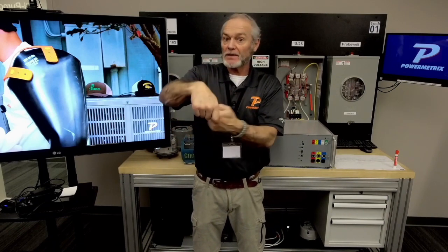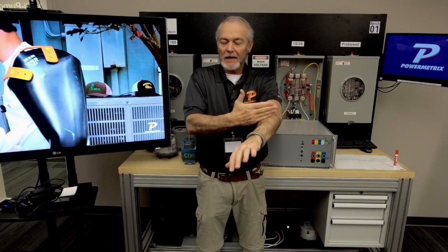Now, when I'm reaching in there to put on my flexes and getting around those conductors, what am I having to do? I'm having to reach in there. I always say, if you can, use the hook to get it around there so you're not reaching. I cringe when I see guys' first move is reaching in with both hands. But if you have the sleeves on, at least if I see a guy sleeved up, I feel better about it. The one I always cringe about is no sleeves. So use the hook if you can to avoid reaching in, but if you do, make sure you're sleeved up with high voltage gloves on.